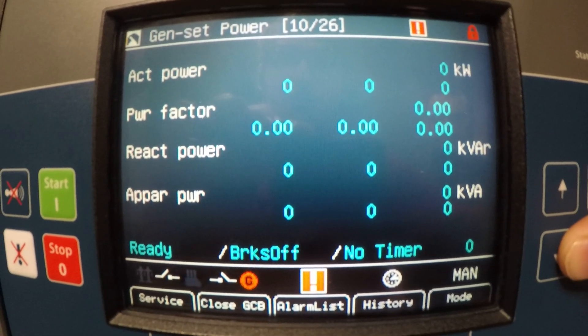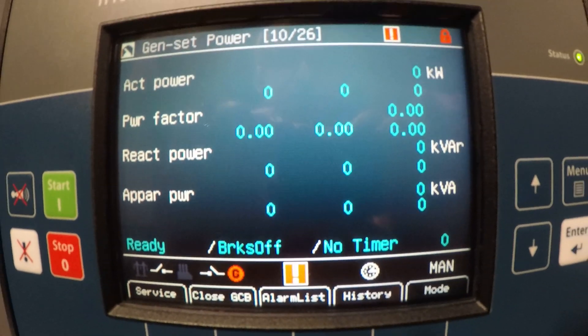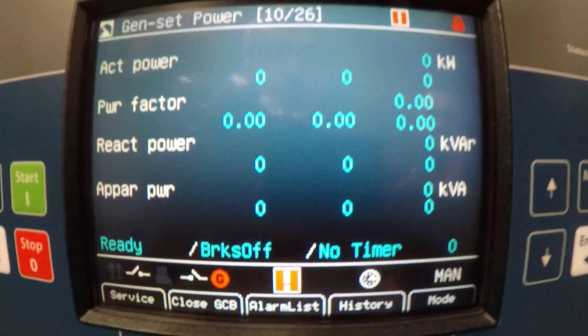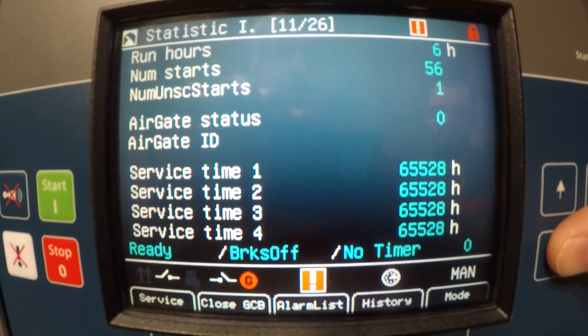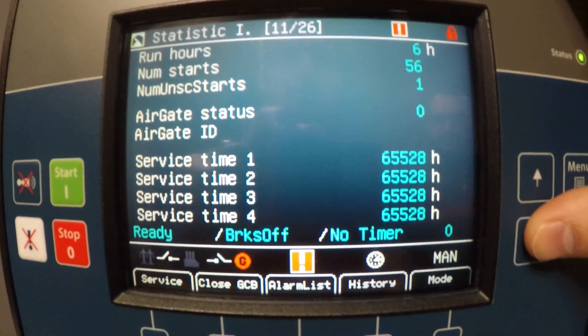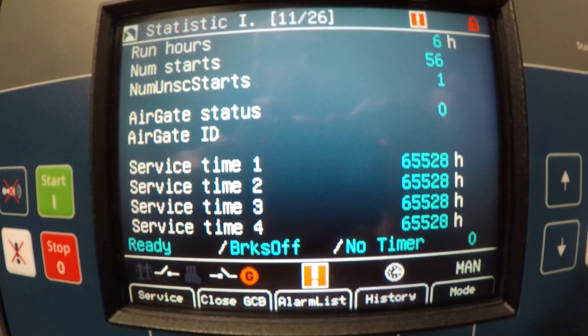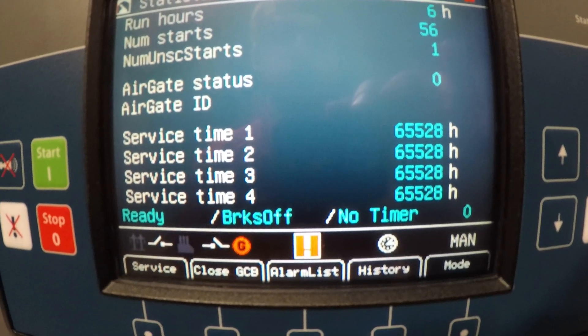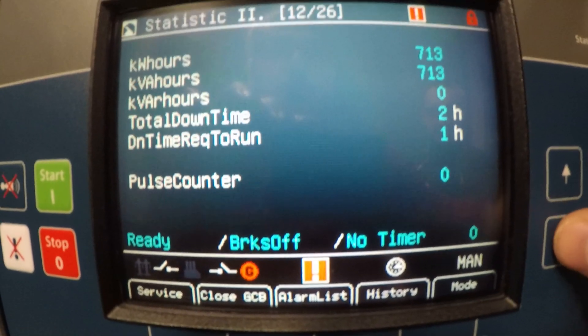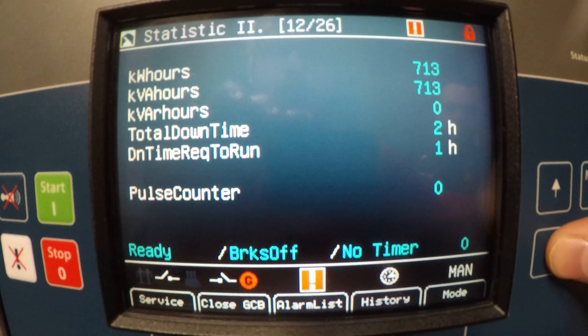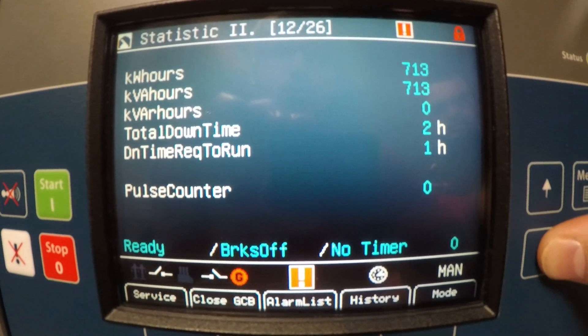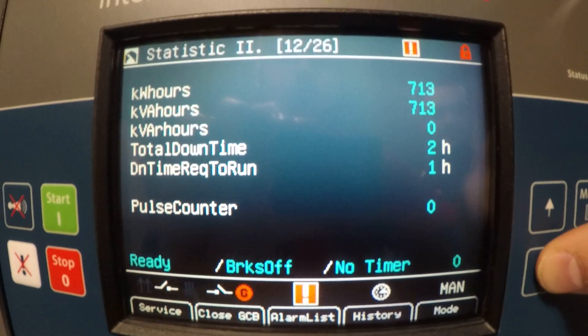You got genset power which is going to show each leg's KW and each individual power factor. You got statistics which will be your run hours, your number of starts, your air gates if you had some kind of wireless system with this, and your service time for maintenance changes. On page 12 we got more statistics: kilowatt hours, total downtime, and your pulse counter.